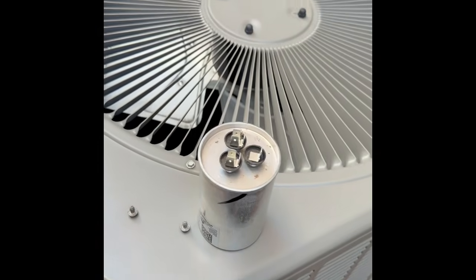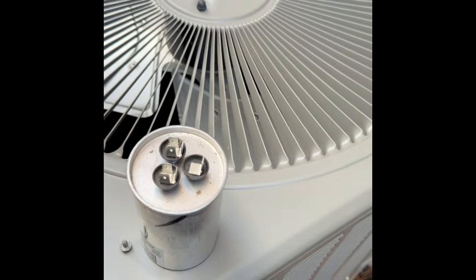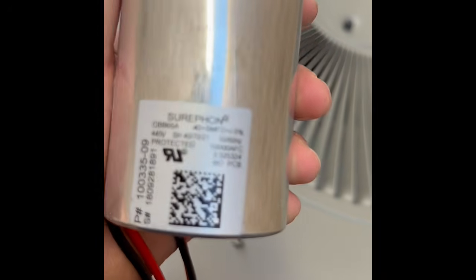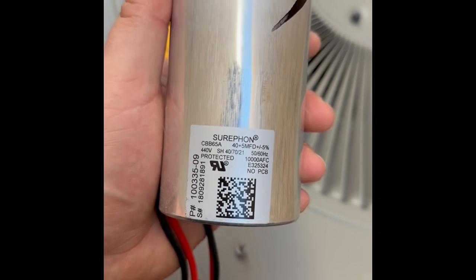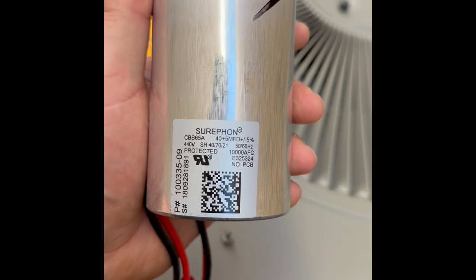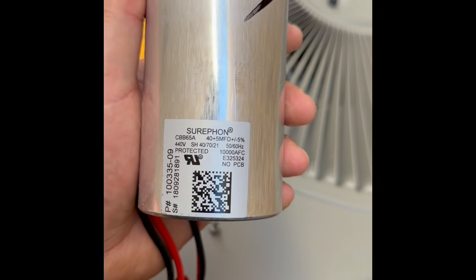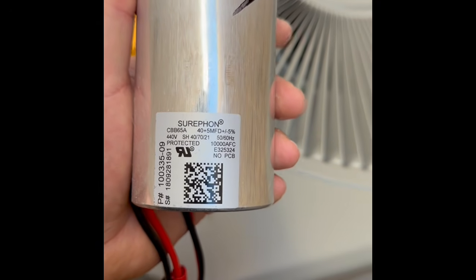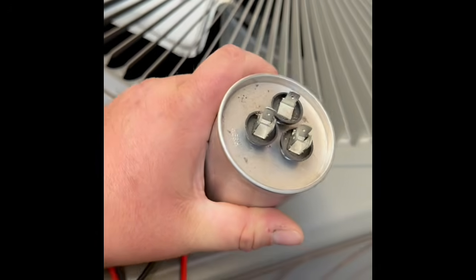All right, here we have our capacitor. We're going to test this capacitor. We're going to test it on the Herm side, and we're going to test it on the fan side. First, we want to check, get it to focus here. We have a 40 plus 5 microfarad capacitor. So we're going to be looking for within 5% of that. Let's see what it looks like.